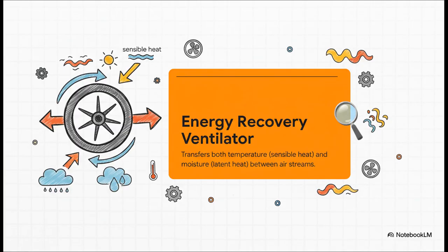Right, so what we're really talking about here is an energy recovery ventilator, or ERV. And this is the crucial point, so listen up. It doesn't just transfer temperature, what engineers call sensible heat, the kind you can actually feel. It also transfers moisture, or latent heat. That's all the hidden energy tied up in humidity. It's like a 2-for-1 energy deal.